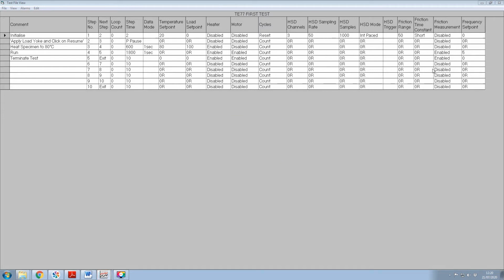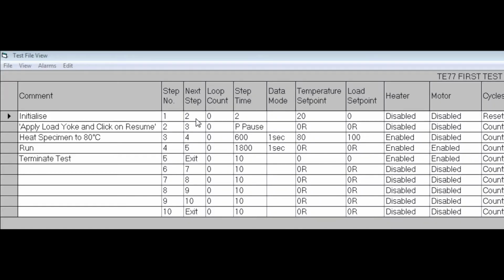It's also sensible to do such things as including a reset of the cycle counter. It is worth at this stage ensuring that the charge amplifier settings for the test have been entered to avoid forgetting to do so later. Finally, it is sensible to set the frequency set point to 0 rather than a positive value, so that the motion does not start instantly as soon as the motor is enabled.